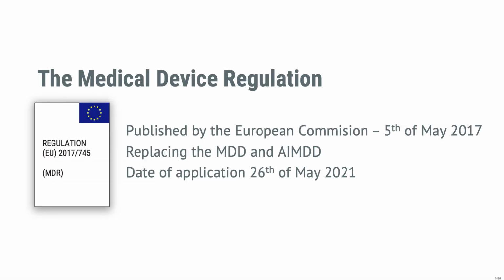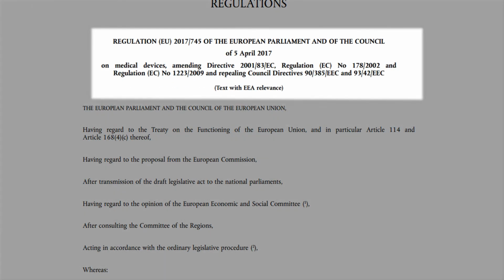So, let's have a quick look into the MDR. This regulation was published by the European Commission on the 5th of May 2017, and thereby replaced the MDD and AIMDD. It entered into force 20 days later, meaning the 25th of May 2017, and it shall apply from the 26th of May 2021. That is the famous date of application, or DOA. And this is what it actually looks like. Not super hot, but it's what we have to live with.